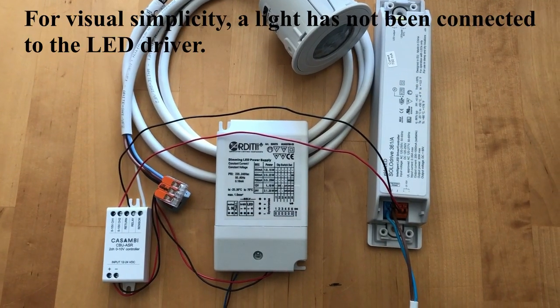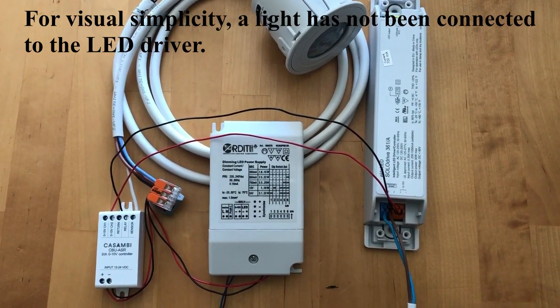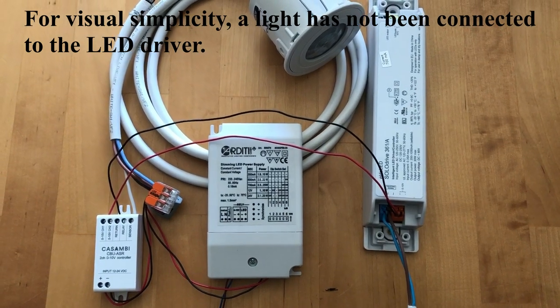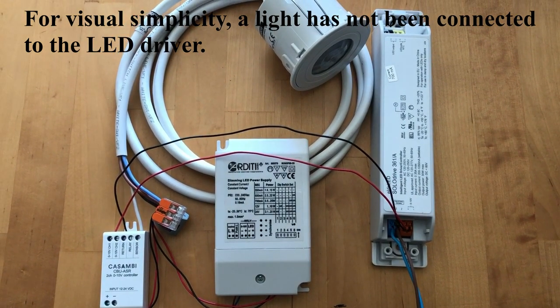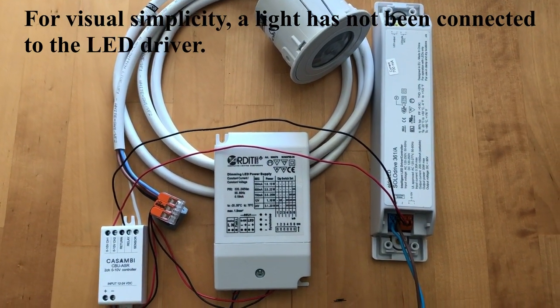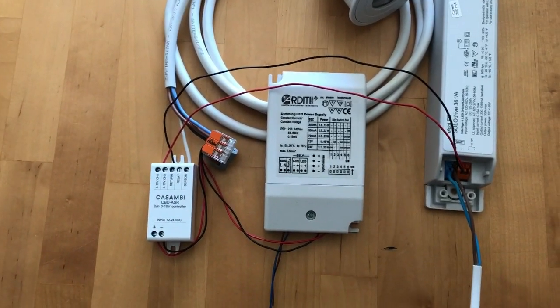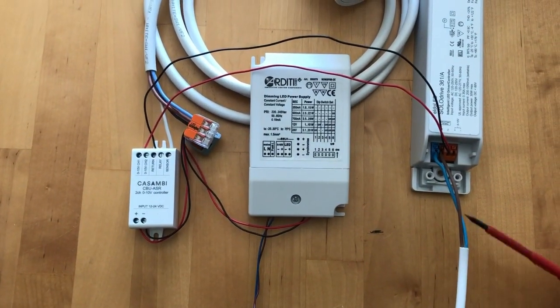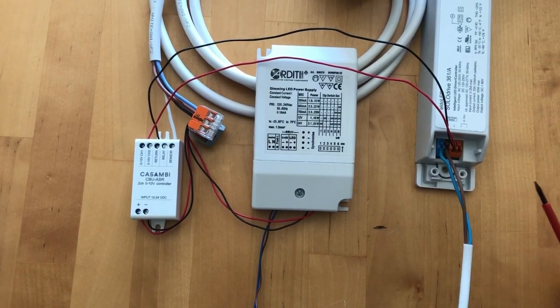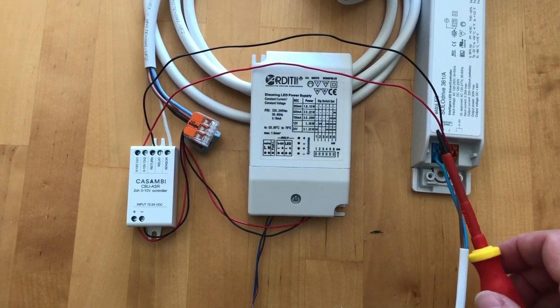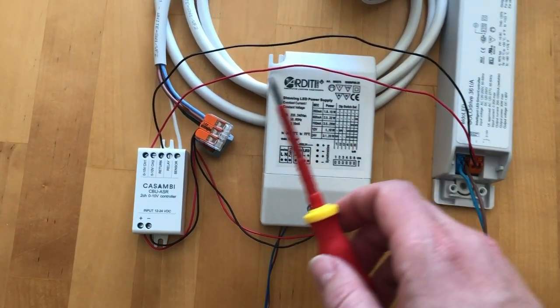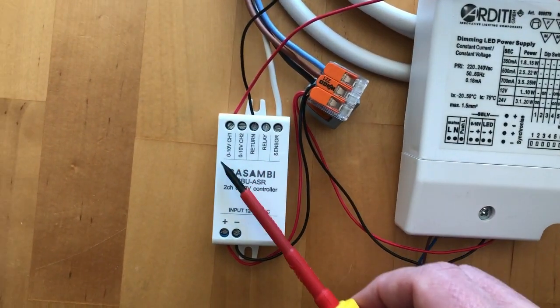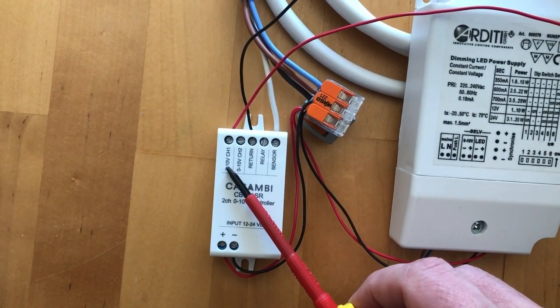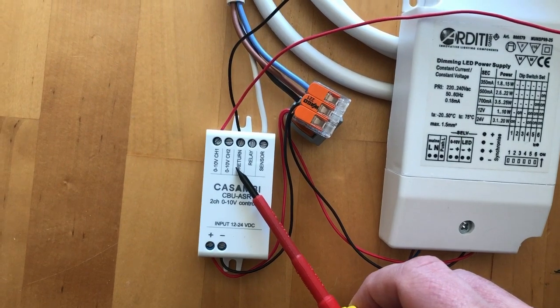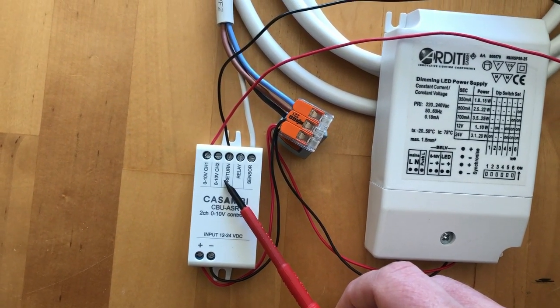This is a quick example of ASR used with a 0 to 10 volt LED driver and a 12 volt passive infrared sensor. The LED driver has its own mains input, and it takes 0 to 10 voltage input or control input from channel 1 of the ASR, and it also uses a return channel or return port.